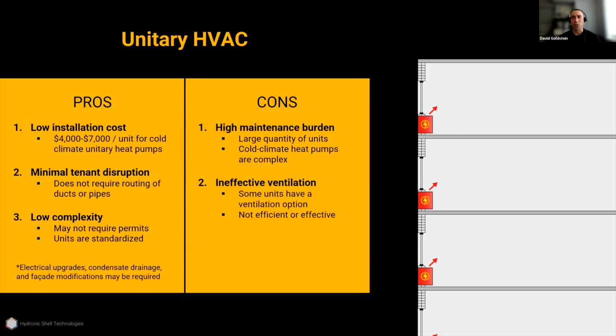And then ventilation, this really important issue in these buildings. Unitary equipment, many of them don't provide any ventilation, but the ones that do, it's not particularly efficient or effective. The way you want to ventilate a building is provide outside air to the living rooms and bedrooms, and exhaust from the kitchens and bathrooms, and then do energy recovery. There's no way to do that with a unitary system.